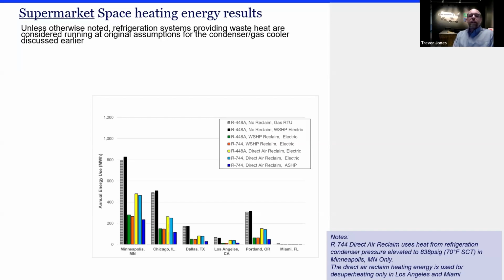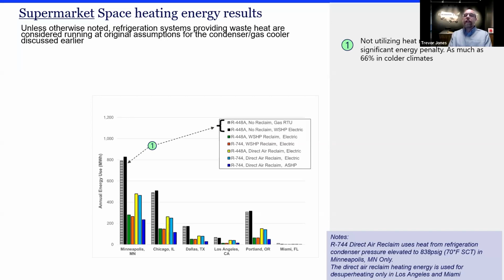This is a complicated graph showing the annual energy usage for both heat reclaim, so heating and refrigeration, for the cities. The cities are listed along the bottom, and then the megawatt hours or equivalent megawatt hours are listed on the y-axis. And the colors denote the options there. So the first two on each are where we have no reclaim used. And so you're paying for all of your heat and all of your refrigeration energy here. So there's a significant energy penalty compared to the use of heat reclaim for the supermarket.